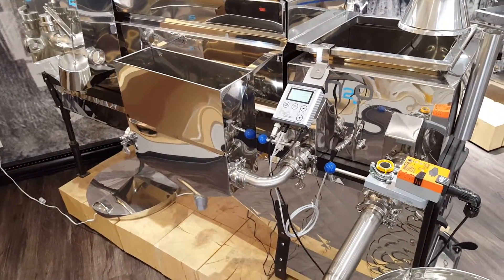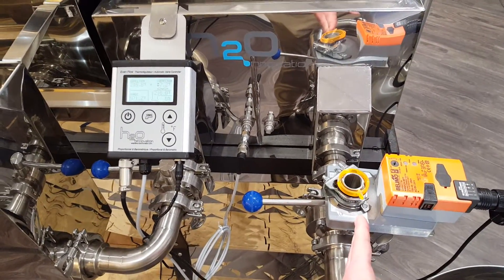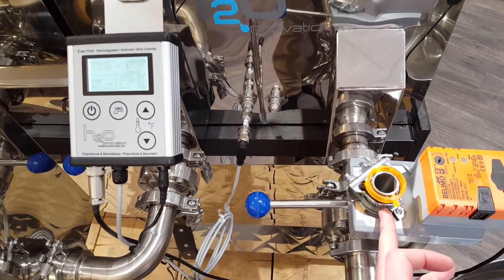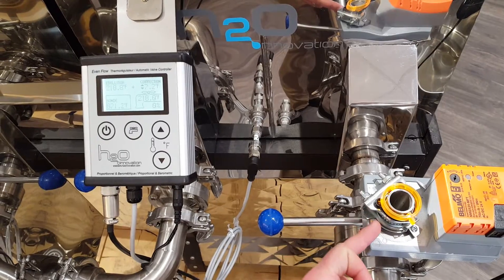Now for this size of evaporator, this one is an 1866, we don't want that valve to fully open, never. So we can actually adjust the fully open position, so our 10 different positions are going to be way closer.